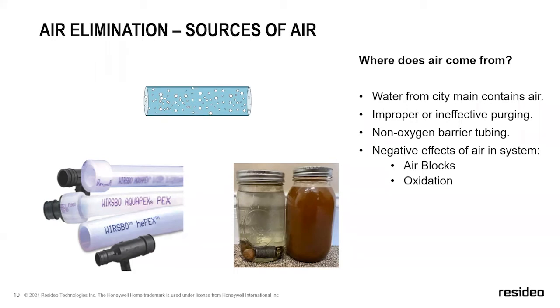For those of you that do in-floor heating systems, you may have 3/8 or 1/2 inch tubing, or even in some systems, 5/16 inch, really small tubing. If you get enough of those air bubbles in the tubes that collect, it'll actually act like an air block. Most of the residential circulators are not capable of creating enough pressure differential to push that air bubble through. So we call it an airlock. When you do your initial purge, it's a good idea to keep the circulators running after you fill and purge it, just to keep everything running through the air eliminators.